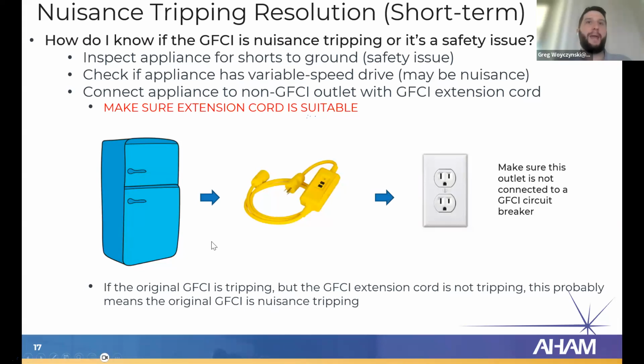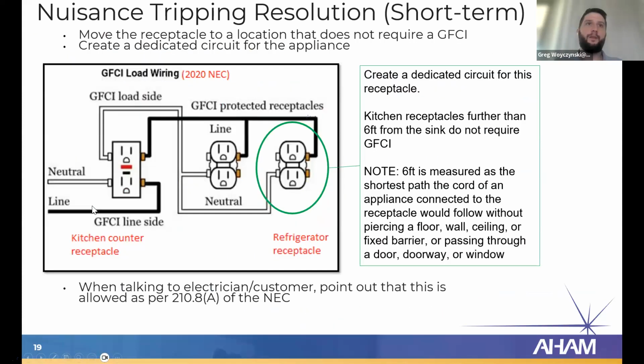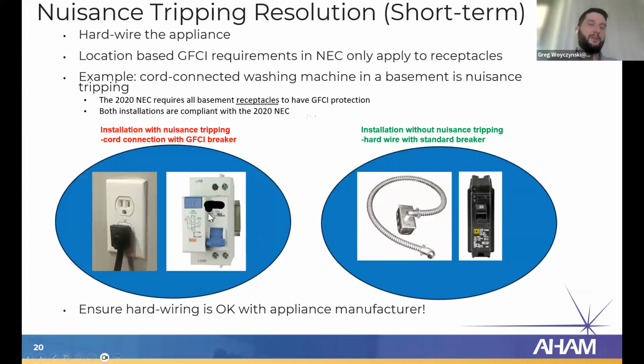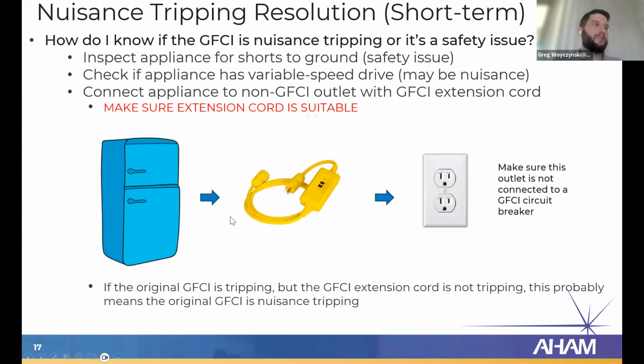So then you can compare the performance of your original GFCI circuit breaker that it was originally connected to and your GFCI extension cord. So if the original GFCI circuit breaker is tripping, but that GFCI extension cord is not tripping, that probably means that the original GFCI circuit breaker is nuisance tripping. So that means that there's a problem with this device. It's tripping on something it shouldn't be. So that's one way you can diagnose to see if it is nuisance tripping. If both are tripping, it could still be nuisance tripping, so that doesn't rule anything out. But the one thing this does tell you, if the circuit breaker is tripping, but this is not tripping, that means there's something wrong with the breaker.